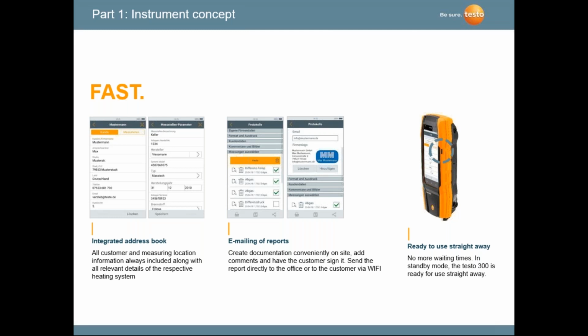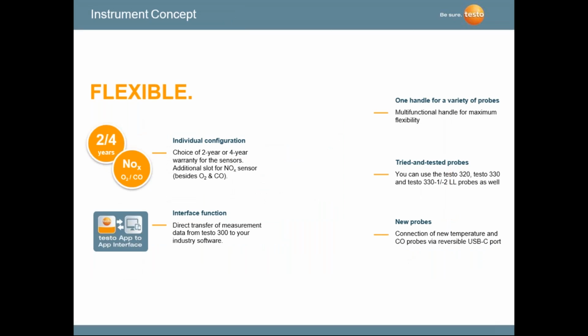You'll see through the operation of the instrument how quickly it is to go into measurement locations. One thing about the newer technology, and I think everyone understands too, is that documentation is getting more and more important, so that not only is the customer information in there, but we also need to know the information on the equipment that we're testing. There's also measurement site location where you can put in the equipment size, equipment type, call job numbers, things of that nature to store your readings. This instrument has the capability of storing thousands and thousands of tests through the use of over many years.